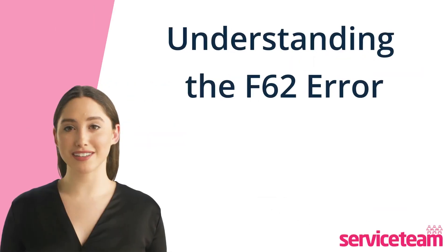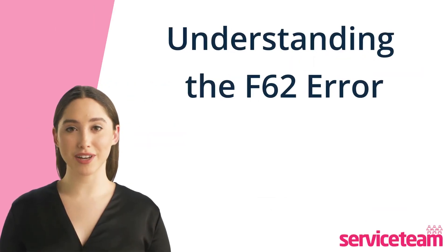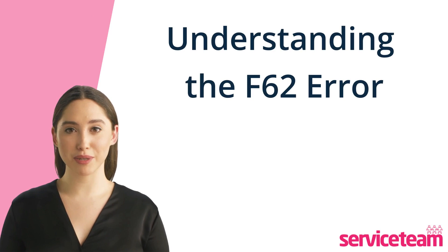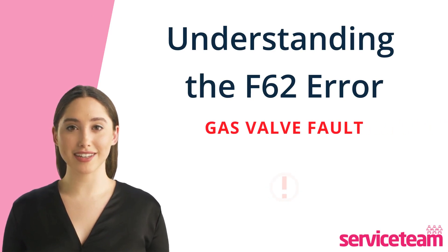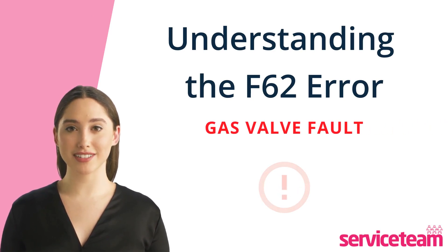If you see the Vaillant F62 fault code on your boiler, it means there's a problem with the gas valve. It especially indicates that the valve doesn't open when the boiler is trying to ignite.